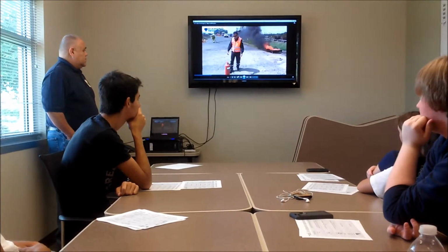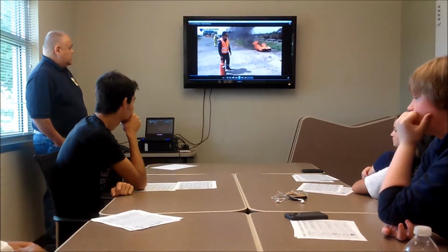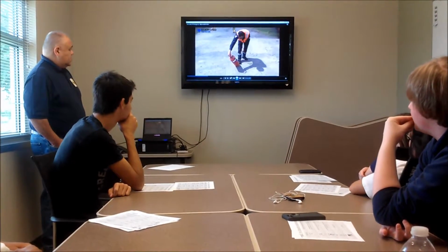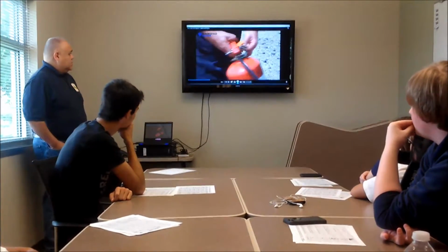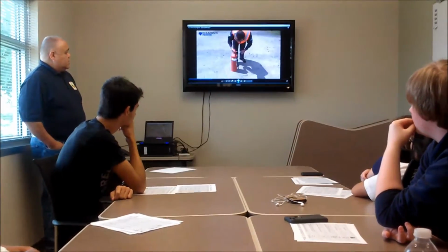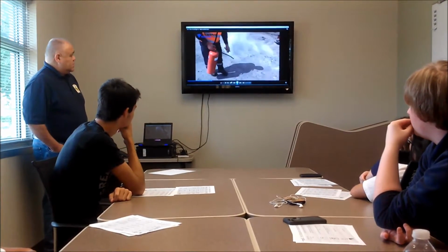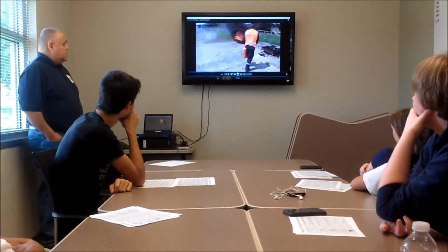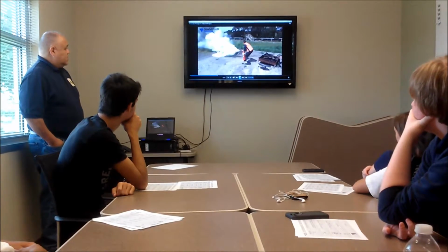There's a fire going at the back there, and he's identified he needs to put that out. He gets up to the extinguisher and looks at the pressure gauge to make sure the extinguisher has enough pressure in it, and the tags are still in. He then removes the safety pin straight out and gives it a test fire off to the side to make sure it's going to work, upwind so he doesn't get it blown back at him. He approaches the fire from upwind, doing a sweeping motion, and lays that right into the top of it.